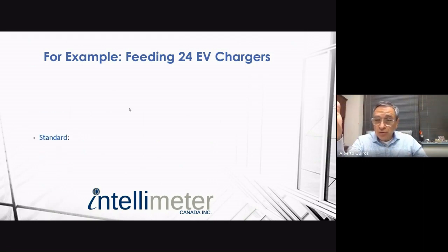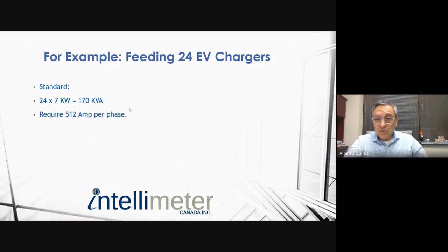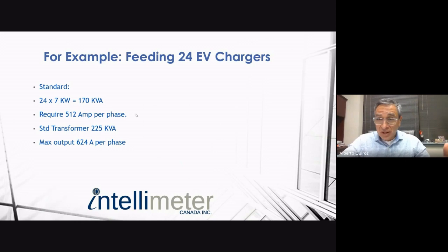So here's an exercise. Imagine you were going to install 24 chargers in a building—you would need 170 kilowatts of capacity. The next size up transformer is the 225 kVA, which you can buy from DAD sales. They'll tell you the commercial sizes are 150 and 225 kVA. So when you go to the 225 kVA, you have to bring in a feeder rated 800 amps, because the current for that transformer is 624 amps.